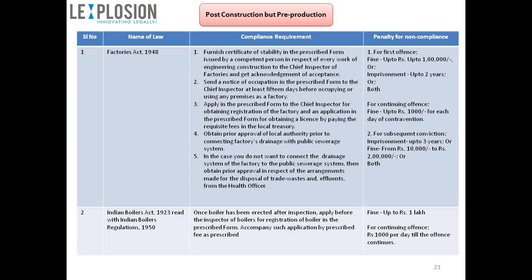We go on to the next legislation, which is the Indian Boilers Act. Under this act, once the boiler has been erected after inspection, you need to apply to the Inspector of Boilers for registration of the boiler in the prescribed form. This has to be accompanied by the prescribed fees.